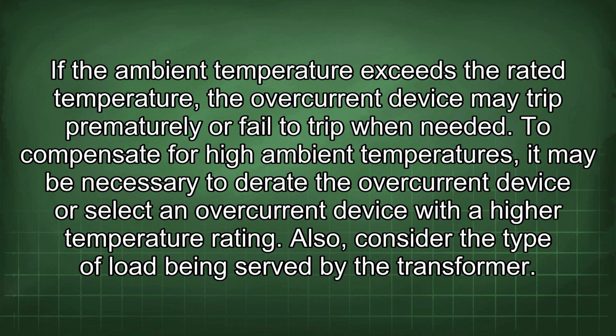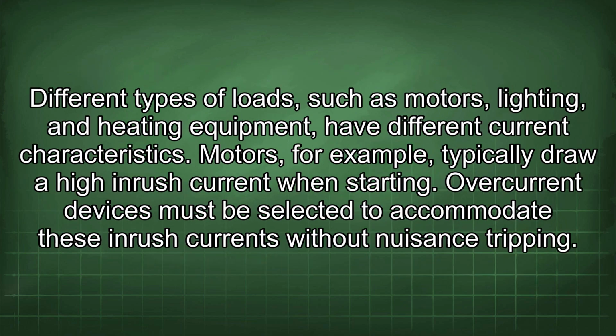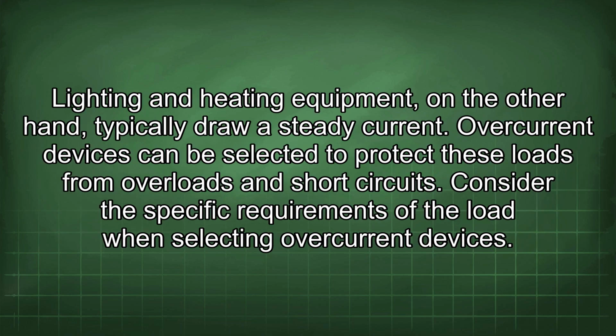Also, consider the type of load being served by the transformer. Different types of loads, such as motors, lighting, and heating equipment, have different current characteristics. Motors, for example, typically draw a high inrush current when starting. Overcurrent devices must be selected to accommodate these inrush currents without nuisance tripping. Lighting and heating equipment, on the other hand, typically draw a steady current. Overcurrent devices can be selected to protect these loads from overloads and short circuits. Consider the specific requirements of the load when selecting overcurrent devices.